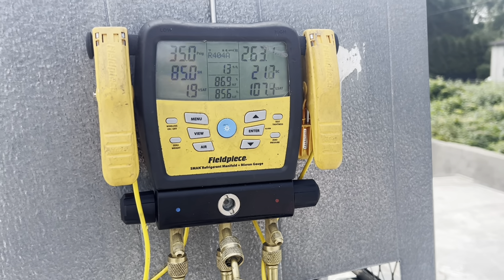Up there is all AC units. She's shaking off the water. More better — not 325 anymore, there's where she's holding. That's about where I want her. The box is still 20 degrees, so that's why that's still a little high. I'm just going to wait for it to hit zero, and that's a wrap.